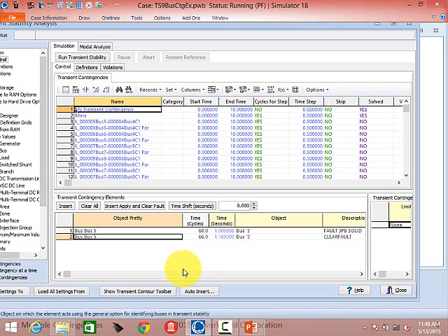So everyone's separate. Just as an extension of that, if you have a three-terminal line, is that defined in here, or is that not defined in here? You have to define it. Okay. So the auto insert doesn't know. So it seems like contingency blocks can't be used. Right. There are no contingency blocks with the transient contingencies. It's completely separate. The blocks are only used with the PowerFlow. So if you wanted something repeated in multiple contingencies, you'll have to manually put those actions in.